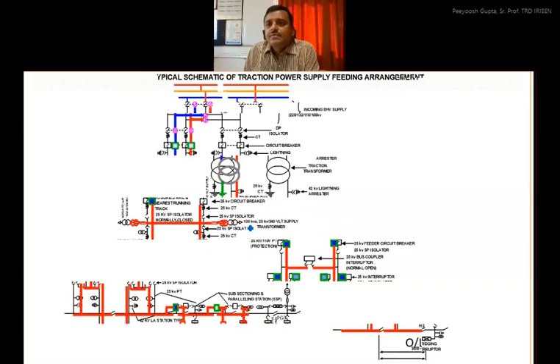So in 2 into 25 kV, instead of 2 phases, we take 3 phases. All 3 phases come to our traction substation, the TSS, and then power comes to the OHE. If you look closely at the pictures shown, there is the catenary, the bottom one is the contact wire, and one more wire, which I have circled, known as the feeder wire, is also running.